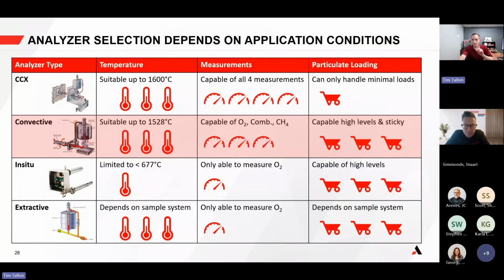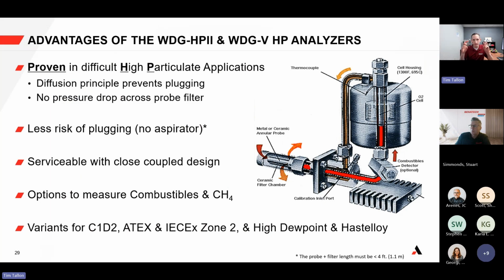And I didn't really say it, Stuart, but the HP stands for high particulate, and it's been proven in high particulate applications. It reduces that risk of plugging because it does not have an aspirator. It's more serviceable with that close coupled design on the process flange—even if it's on the process flange, it's more serviceable. Again, you have the other measurements like I mentioned, and other variants for hazardous area. So that's why it was invented, and I hope that answered that question.